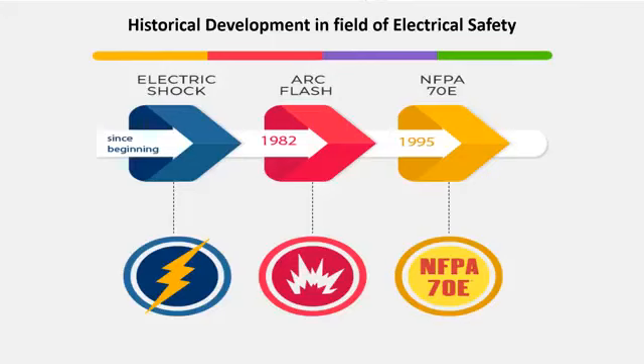So in most of the companies which you visit, you won't find those risk assessments performed, the arc flash risk assessment. The outcome of those risk assessments is the boundaries requirement and the correct amount of personal protective equipment (PPE) requirement. So till now, most organizations do not recognize arc flash as a hazard, and they don't recognize that it is controllable, and that you can provide a certain amount of personal protective equipment in order to safeguard employees as well.